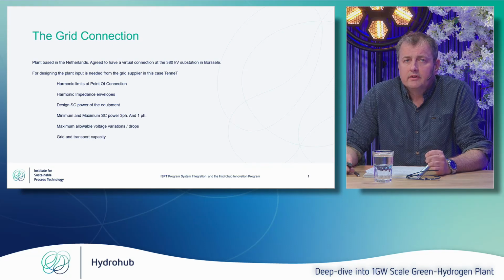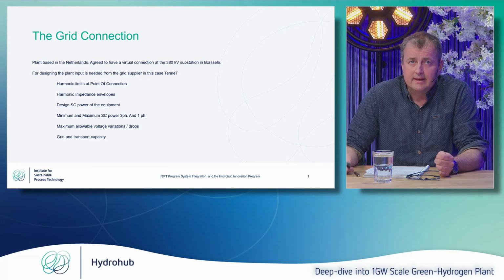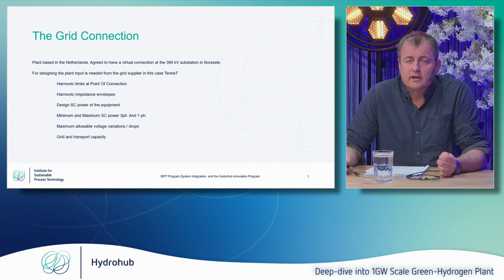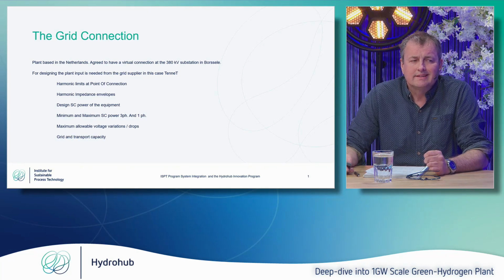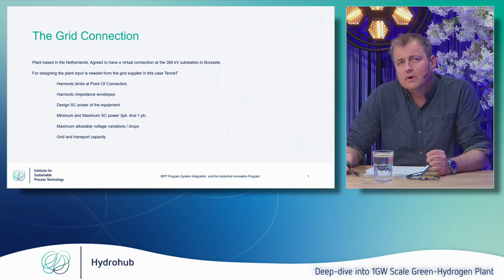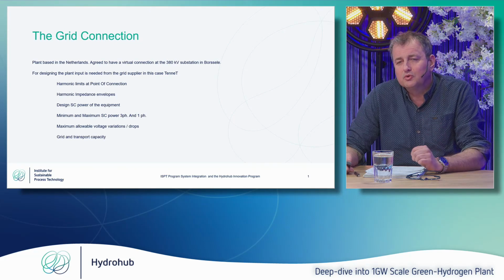The starting point is the IEC standards and the Dutch grid codes. The IEC 61000 standards and the technical reports, that's really the starting point. Besides this, TenneT also had a list with limits for each and every harmonic from the second up to the 50th harmonic. So we also had to fulfill those requirements. And what is also very important is those requirements were for all kinds of operations. So in this case, we really had a flexible operation from 0 to 100 megawatt, I wanted to say, but to 1 gigawatt, of course.